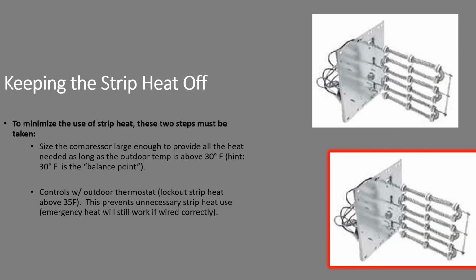Keeping the strip heat off, how do we do it? We size the compressor large enough to provide heat for the house all the way down to 30 degrees. 30 degrees is a balance point we like to see. It gives you a nice mix of capacity and a nice mix of efficiency and a nice happy homeowner that isn't freezing when it gets cold outside.